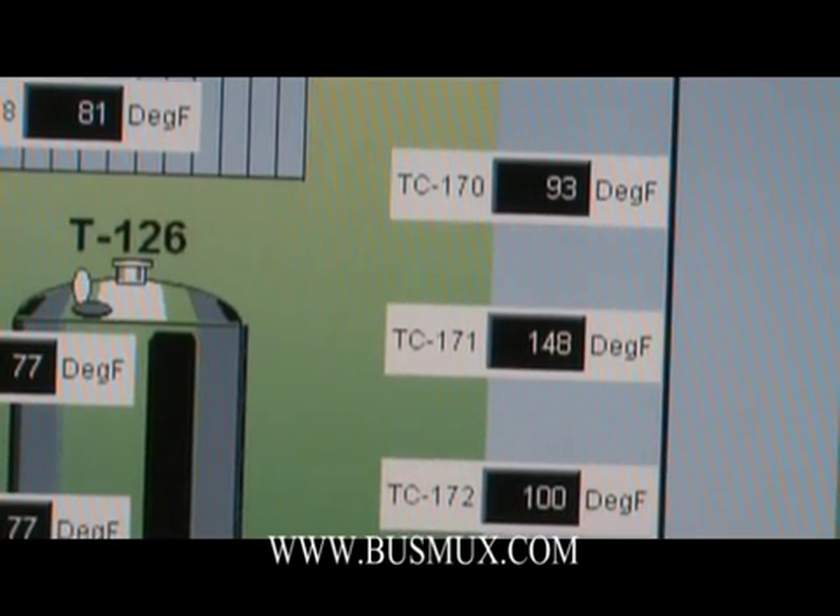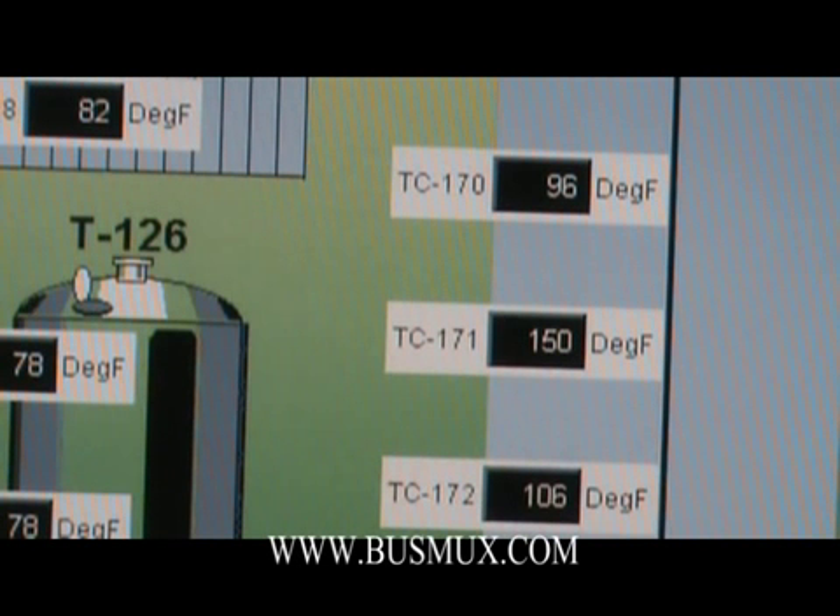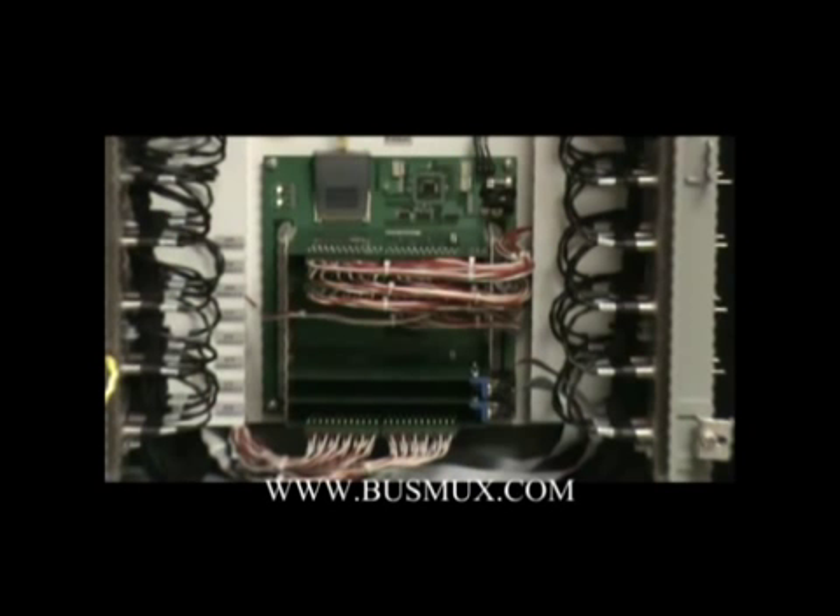The scan rate is considerably faster than some existing systems. It is known to scan over 1,800 thermocouples in less than 6 seconds. You have two different methods of connecting to a BusMux card: either through a terminal block or a 24-pin Centronic-style connector.